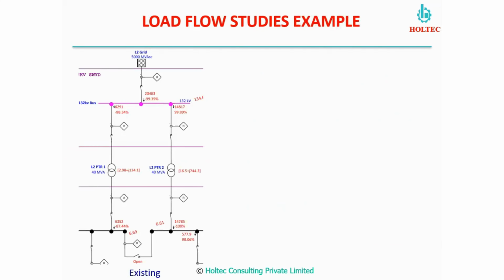Now, next is an example. Here, this is a portion of a study result in one of the projects. This is the existing situation where the power is being received from the grid, and we have a main receiving station where we have two different buses where the bus coupler is in open condition. So the load is being there on both the power transformers. So here the overall power factor we are able to maintain.